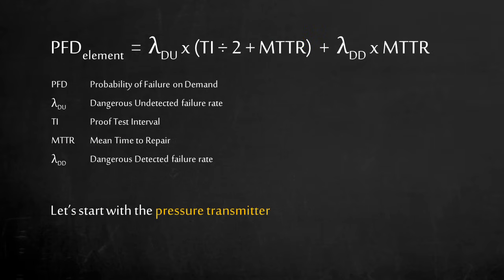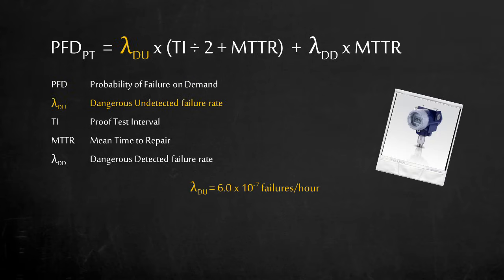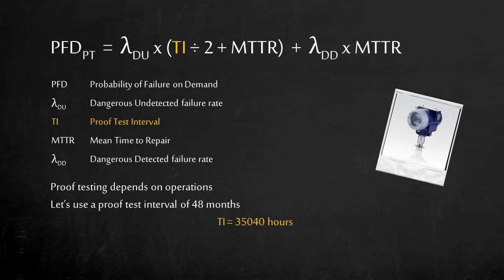Let's try it out on the pressure transmitter, which is our sensor element. The pressure transmitter has a dangerous failure rate of 0.6 hidden failures per 1 million hours of operation. Proof testing depends on operations. This is crucial and requires commitment from operation and maintenance. Let's say the crew performs a proof test every 48 months. This is to ensure the transmitter can produce the alarm signal in a high-pressure condition. Since all the variable units need to be consistent, we'll convert 48 months into 35,040 hours.